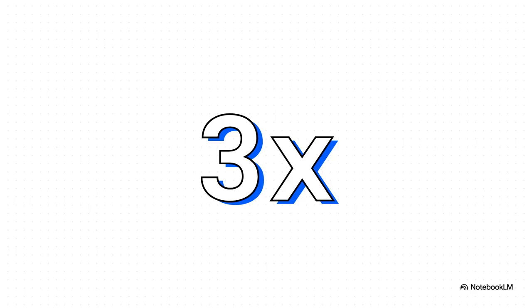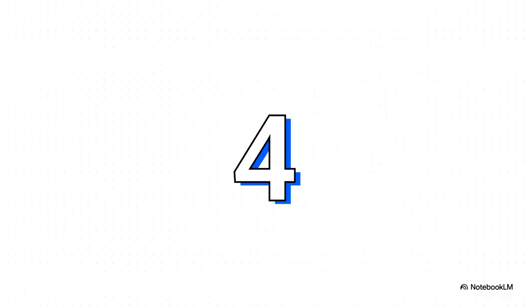This simply means the image of the mass looks 3 times wider than it actually is. Next up, we have to deal with our depth perception. Remember how the BIO headpiece used those prisms to squeeze our baseline 60mm PD down to 15mm? Well, 60 divided by 15 is 4. Because our effective baseline for stereopsis was compressed by a factor of 4, our depth perception is mathematically reduced by a factor of 4.